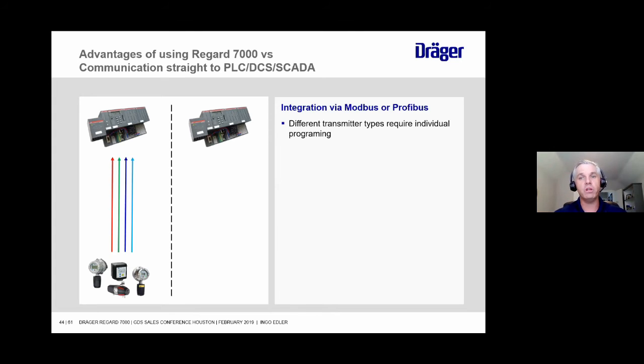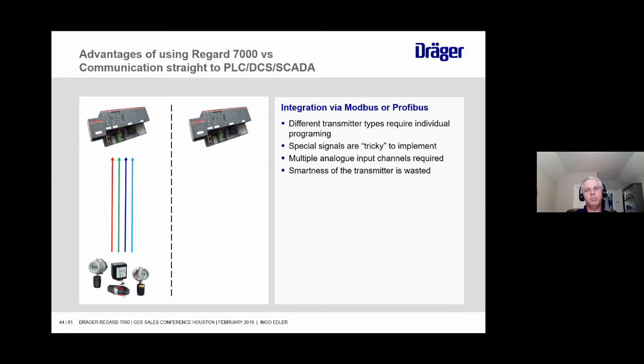Different transmitter types require different programming. Even the Draeger stuff. So those special signals I was talking about before, 3 milliamps means this, 2 milliamps means that. Each one of our transmitters has different special signals based on the type of transmitter that it is. So it would be very time consuming for someone who's not familiar with our stuff. I'd have to understand how to do that, look in a manual, and go and program those special signals into the PLC or DCS. Like I mentioned, special signals are tricky to implement, multiple analog input channels are required, and it basically wastes the smartness of the transmitter.